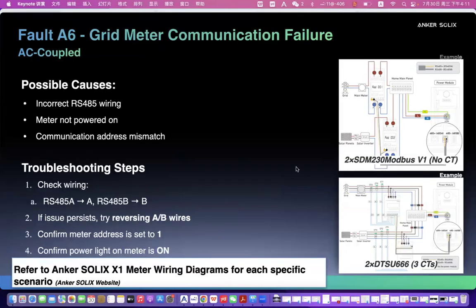And the next scenario is the A6 error. It also frequently happens. What does this mean? It's a grid meter communication failure. This part means this cable, because the CTs also have the communication cable. Make sure it's connected to the red part, from the white blue, white blue, white blue. It's for the CT communication cable. Make sure this is correct. This is one thing. And the second thing is make sure for the grid meter we connect to the 24 and 25 port for this meter.